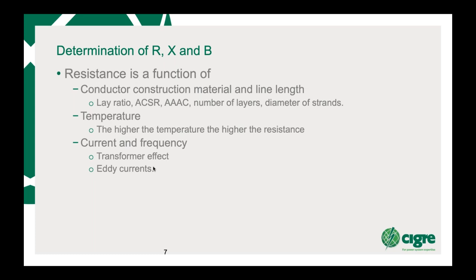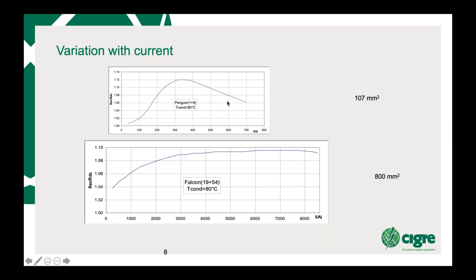Now, normally in the past, the frequency was considered quite important, and that increases the resistance by about 2%. But if you look at certain conductors, you'll find that the current, in fact, is a bigger increase in resistance than the frequency effect, and especially in single layer conductors. These are the conductors used on MV lines. So your Hare, Mink, this is a Penguin.